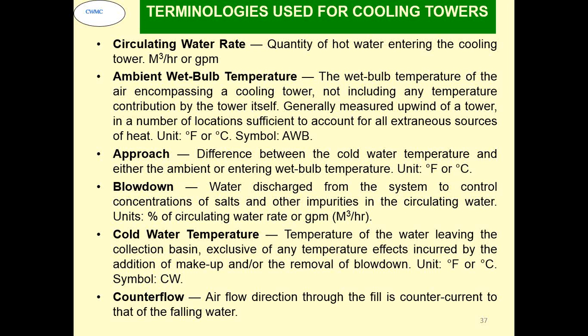Ambient wet bulb temperature is the wet bulb temperature of the air surrounding the cooling tower, not including any temperature contribution by the tower itself. It is generally measured upwind of a tower in a number of locations sufficient to account for all extraneous sources of heat. Units are degrees Fahrenheit or degrees centigrade. The symbol generally used is AWB.